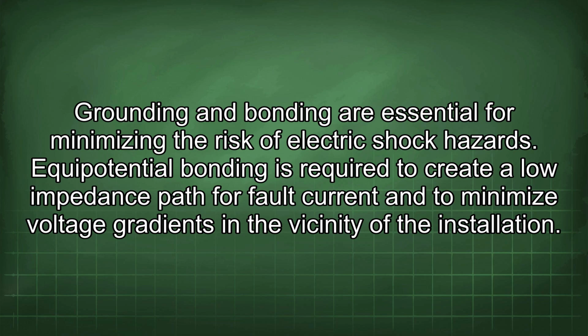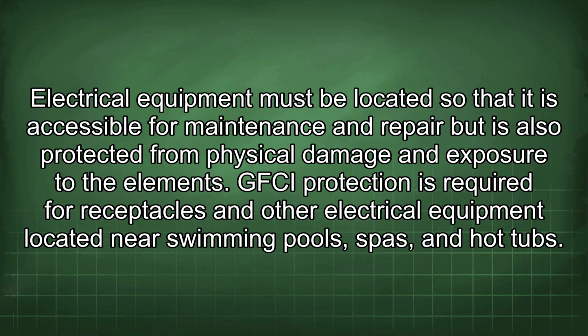Grounding and bonding are essential for minimizing the risk of electric shock hazards. Equipotential bonding is required to create a low impedance path for fault current and to minimize voltage gradients in the vicinity of the installation. Electrical equipment must be located so that it is accessible for maintenance and repair but is also protected from physical damage and exposure to the elements. GFCI protection is required for receptacles and other electrical equipment located near swimming pools, spas, and hot tubs.